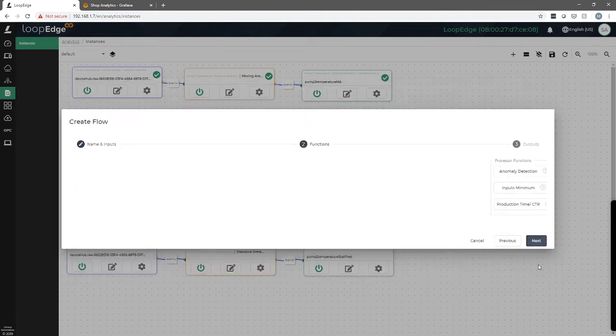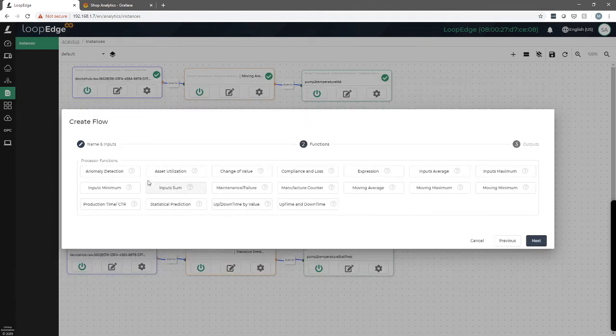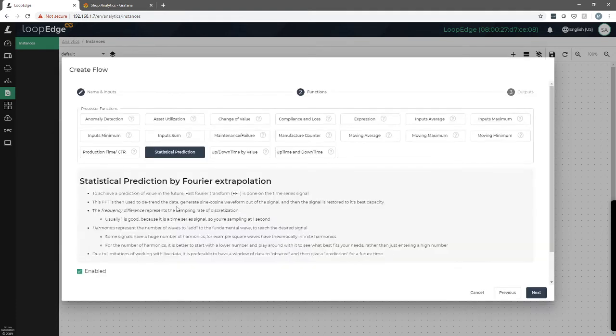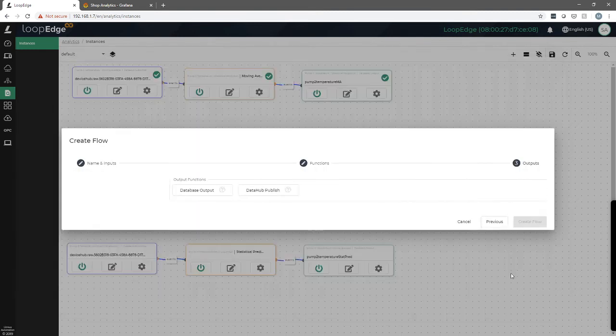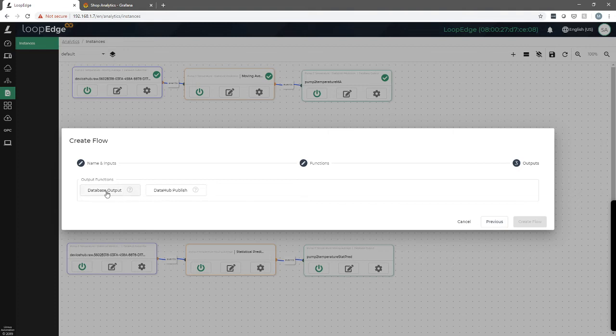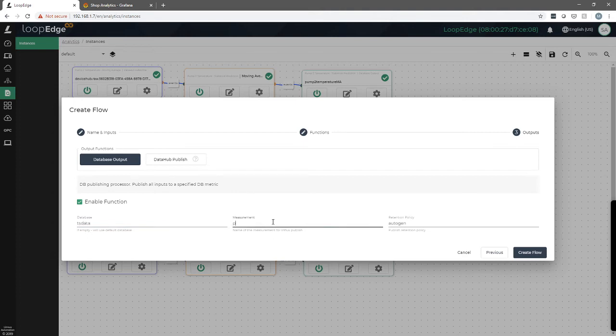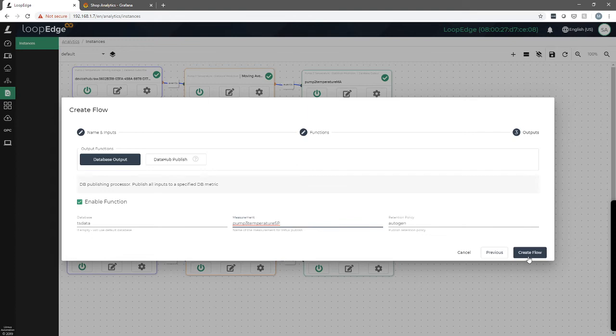We click next and these are all the different processor functions that you can choose from. So what we're going to pick is statistical prediction, and then we will hit next and we will choose database output for ours. The database will be TS data, that's our default Litmus Edge database, and we'll call this pump three temperature SP, and that could be any name that you want. It's just a name it's going to write to in the database. And we go create flow.